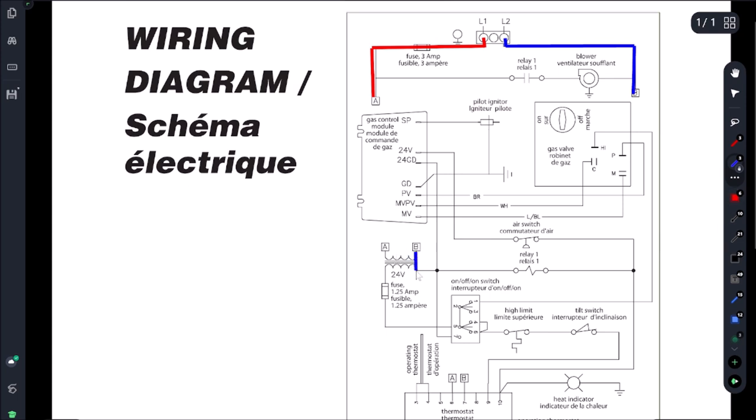So here's the transformer, we're going to bump it down to 24 volts and then we're going to come through here onto our pin 7, and then our hot side of our 24 volts is going to come through here, pin 5.